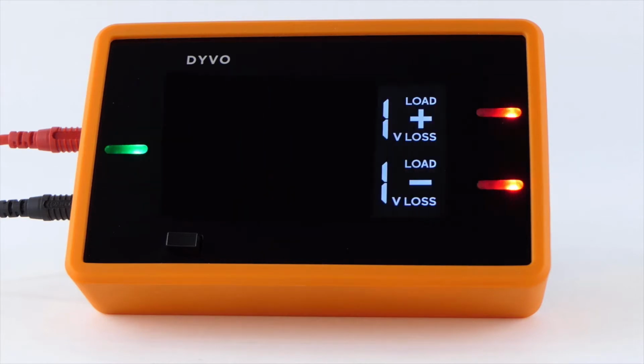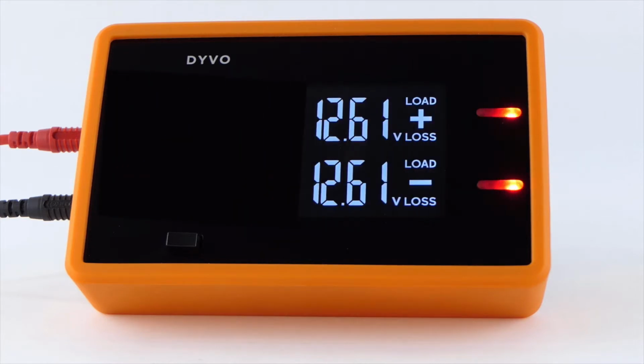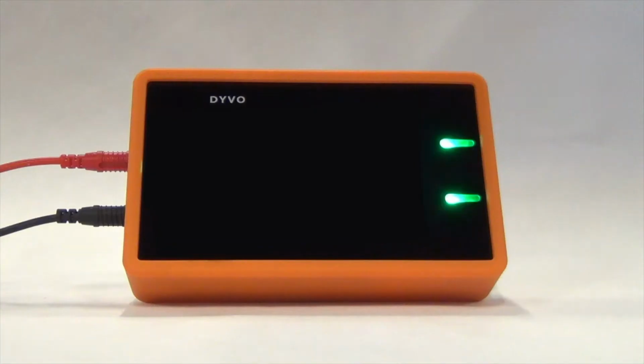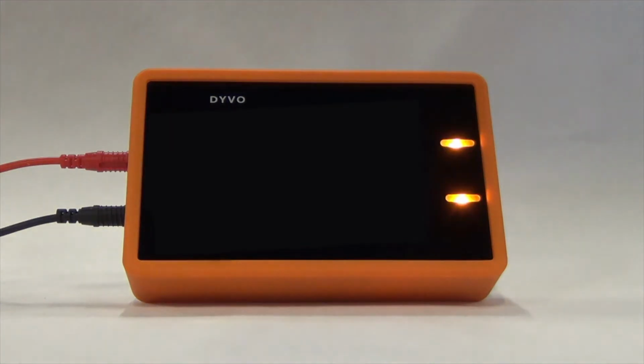On the right side of the screen, we have 2 LEDs and 2 numeric values. The top value and LED are for your positive circuit, any positive circuits you want to test, and the bottom right value and LED are for the negative or ground circuits you're testing. For both positive and negative circuits, we have 3 LED colors: green means a low voltage drop, yellow means a medium amount of voltage drop, and red means a high voltage drop.